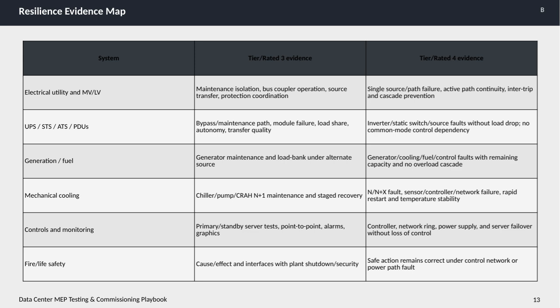For generation fuel systems, Tier 3 requires testing under alternate source conditions, including generator maintenance and load bank testing. Tier 4 expects the system to handle generator, cooling, fuel, or control faults while still maintaining remaining capacity without causing overload cascades. Mechanical cooling systems at Tier 3 cover N+1 maintenance for chillers, pumps, and CRAH units along with staged recovery processes. At Tier 4, systems must handle faults including sensor, controller, or network failures, and support rapid restart while ensuring temperature stability.